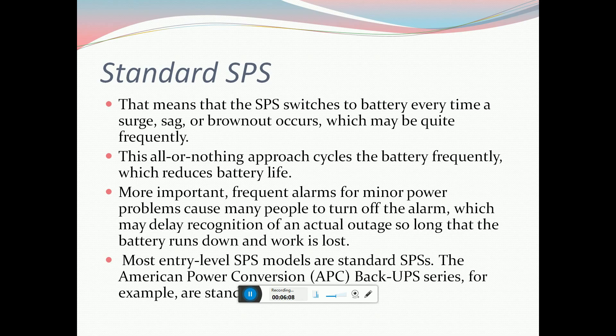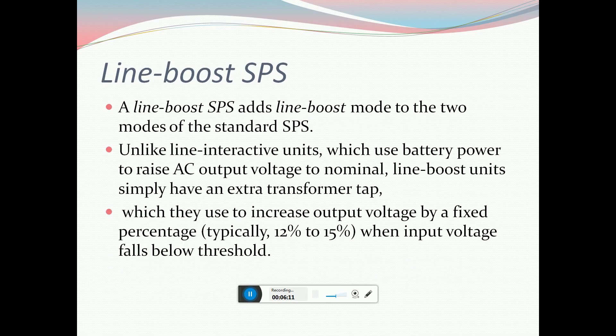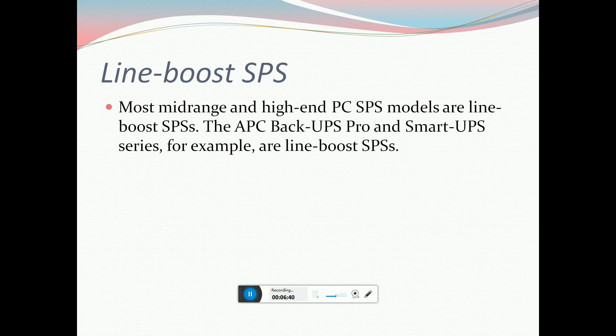A line boost SPS adds a line boosting mode to the two modes of the standard SPS. Unlike line interactive units that use battery power to raise AC output voltage, a line boost unit simply uses an extra transformer tap that increases output voltage by a fixed percentage — typically 12% to 15% — when input voltage falls below a threshold. Most mid-range and high-end PC SPS models, such as the APC Back-UPS and Smart-UPS series, are line boost SPSs.